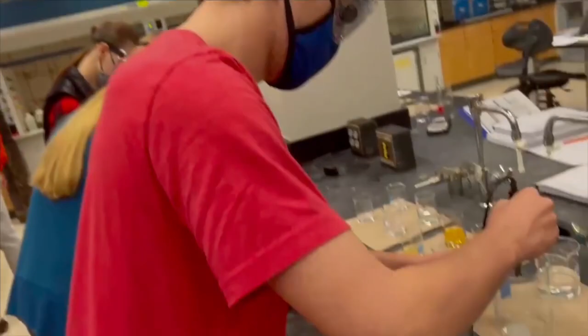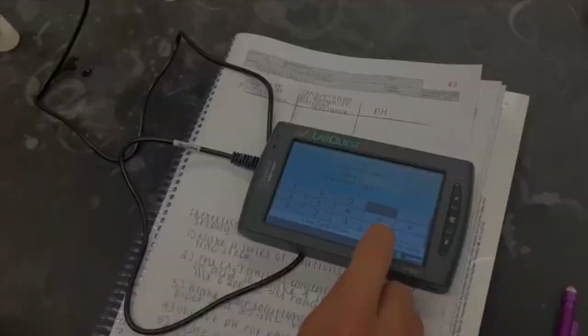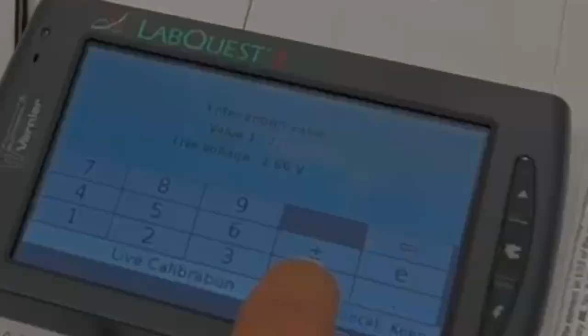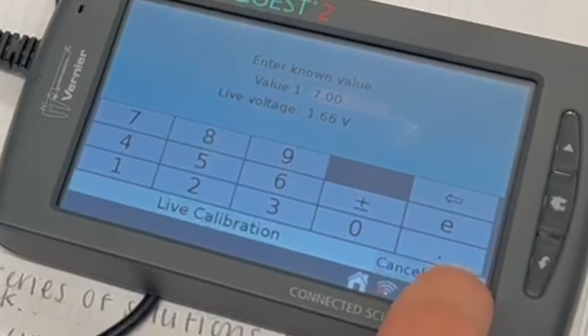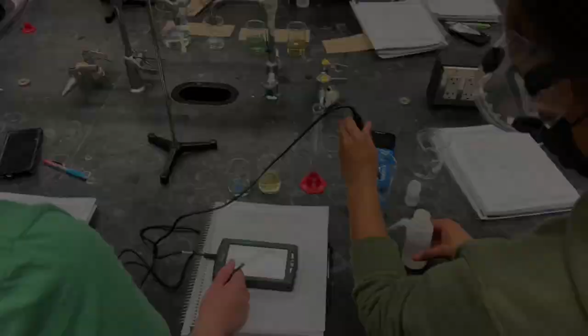First thing we had to do when working with the pH probe was properly calibrate it using a pH 7 buffer solution and a pH 4 buffer solution. To start, you must carefully remove the probe from its container and rinse with distilled water. Then you can place it in the pH 7 buffer solution and input that value into your meter.